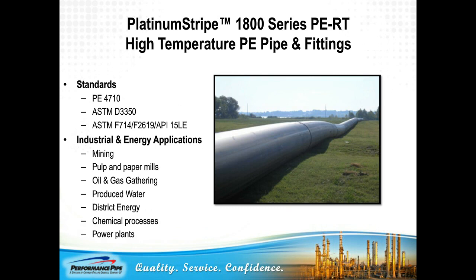PlatinumStripe 1800 series PERT high temperature PE pipe and fittings. Let's review the standards for this new product. PlatinumStripe 1800 series PERT is a PE4710 material with an established cell classification per ASTM D3350, and it is produced to meet ASTM F714, F2619, and API 15LE. The product can also be manufactured as needed to ASTM D2513 and D3035.